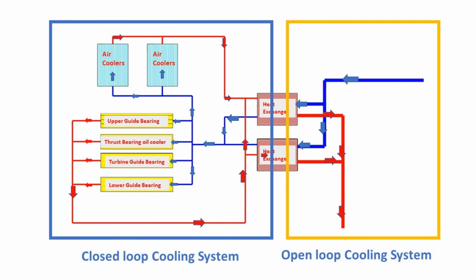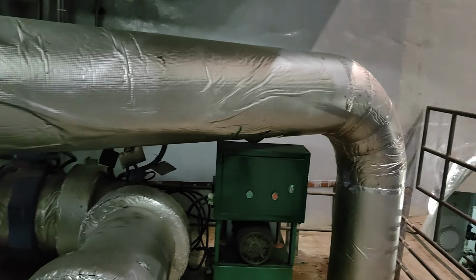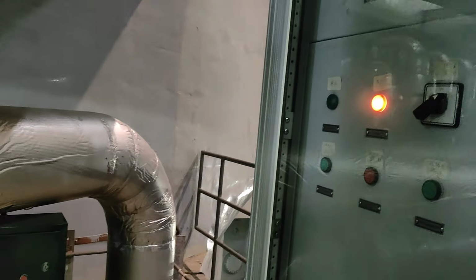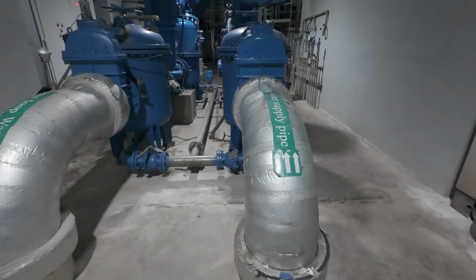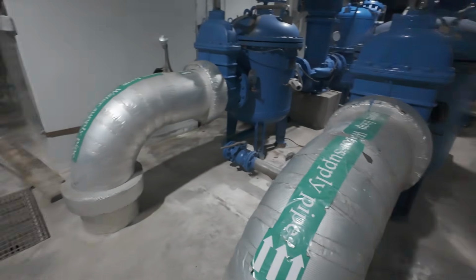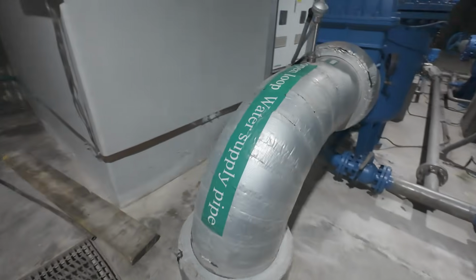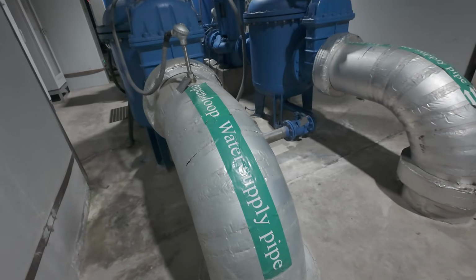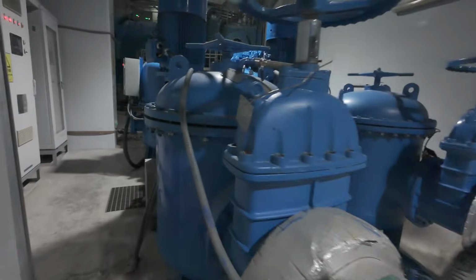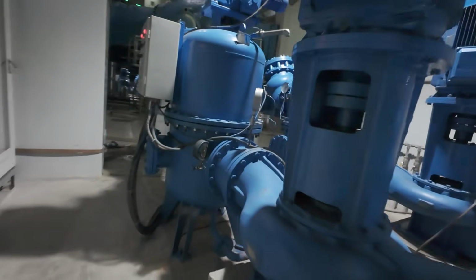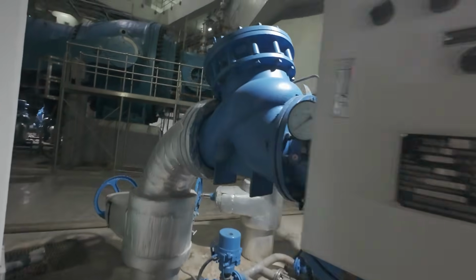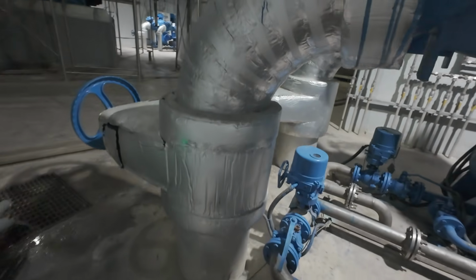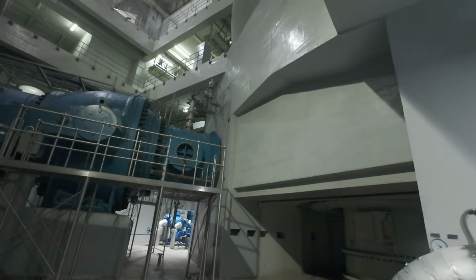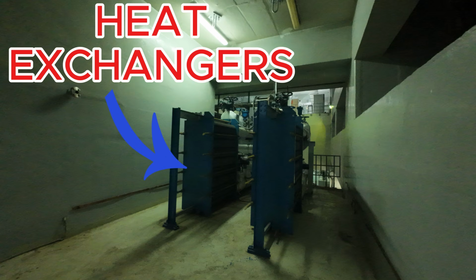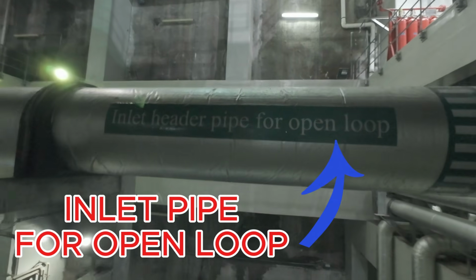Now, let's follow the complete path of the cooling water. Step one, cold water is taken from the tailrace or reservoir. This becomes the open loop water, but before entering the system, it passes through manual strainers. These remove leaves, stones, large debris, and next is the open loop pump. It increases water pressure and circulates the water. Usually, one pump runs continuously while another remains on standby. After the pump, water passes through automatic strainers. These remove small particles and protect the heat exchanger from choking.